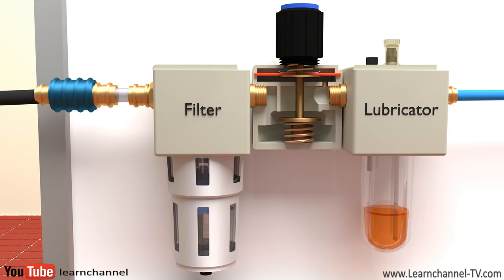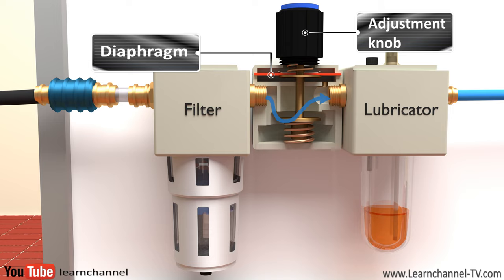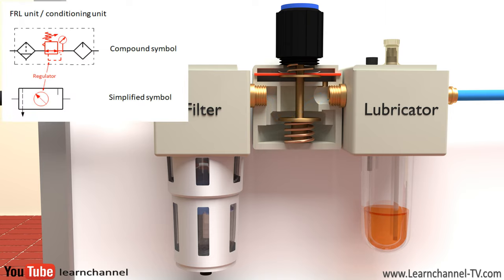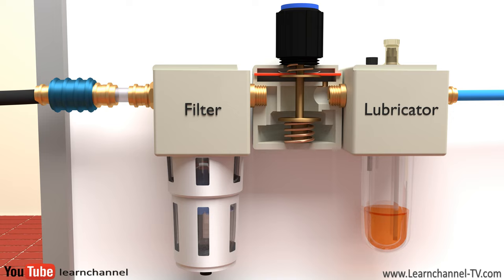It is essential to supply the air at a constant pressure, regardless of upstream flow and pressure fluctuations. Pressure regulators, also referred to as pressure-reducing valves or PRVs, ensure the consistency of the dynamic working pressure at a specific value. There are several types of air regulators. The diaphragm-type regulator is commonly used in industrial pneumatic systems, so we'll take it as an example. As the name suggests, the pressure is regulated by the movement of the diaphragm.